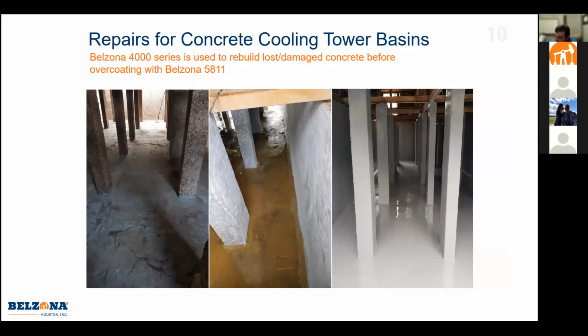Say you have these vertical columns. We can apply up to about 3 to 4 inches vertically without any sagging, and then we'll go back with that immersion grade sealant. As you can see on the far right, that's our 2-coat system back on top, the same one we'd put on a metal cooling tower.